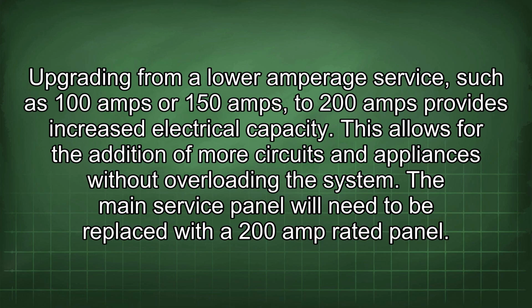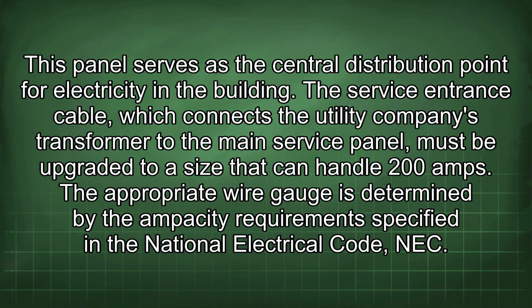The main service panel will need to be replaced with a 200 amp rated panel. This panel serves as the central distribution point for electricity in the building. The service entrance cable, which connects the utility company's transformer to the main service panel, must be upgraded to a size that can handle 200 amps. The appropriate wire gauge is determined by the ampacity requirements specified in the National Electrical Code (NEC).